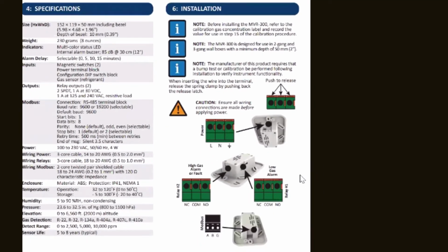And then the connections to the MVR-300, on one end, you're going to have both the Modbus and the power. And then on one of the sides, you're going to have a high gas alarm and a low gas alarm. You have to have the 120 volts coming into it, and you have to have a Modbus input since you're going to be configuring to the controller. I'm not sure if there's going to be auxiliary systems for the alarms, but these are typically connected to auxiliary ventilation. If the gas detector detects a low alarm or a high alarm, sometimes these relays can be used to turn on added ventilation, or they can be used to, go ahead.